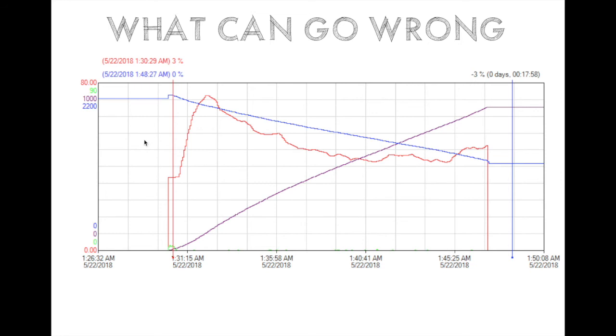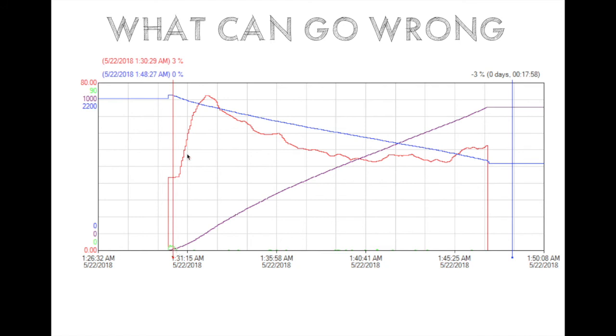So what can go wrong? In this example, I show an example of how the screw speed was bouncing near zero because there is a suction pulling out the powder. We call this flooding through or around the screw. So there is a suction that is just making the powder free-flowing through the screw and inside the snout of the screw being injected into our process. So even though this green, which is the screw speed, it starts running, but it quickly realizes that it needs to slow way down. And even though it comes back down to zero, the flow rate is going higher and higher and it is just in this uncontrolled state where the target that it's trying to get to is where it started. It's trying to come down and down, but it can't get the screw speed anywhere lower than zero.